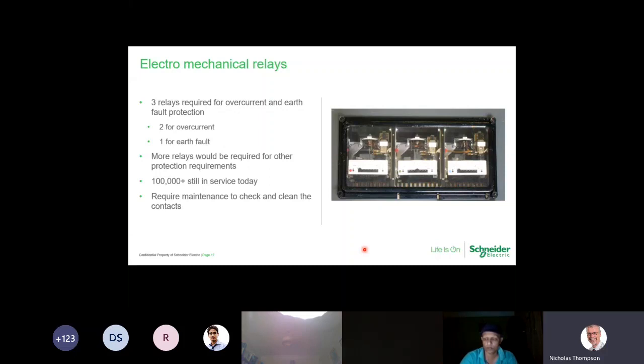So for the basic protection of overcurrent and earth fault, you needed 3. So 2 did overcurrent, 1 did earth fault. So that is very similar to what we've just seen in time limit fuse. So we've got 3 relays, we've got 3 trip coils, and ultimately we've got 3 CTs. Now, it's not surprising to find out that there are literally hundreds of thousands of these still in service today, and it's only in a relatively short space of time that London Underground moved over to the modern digital relays when they were upgrading their entire electrical infrastructure.